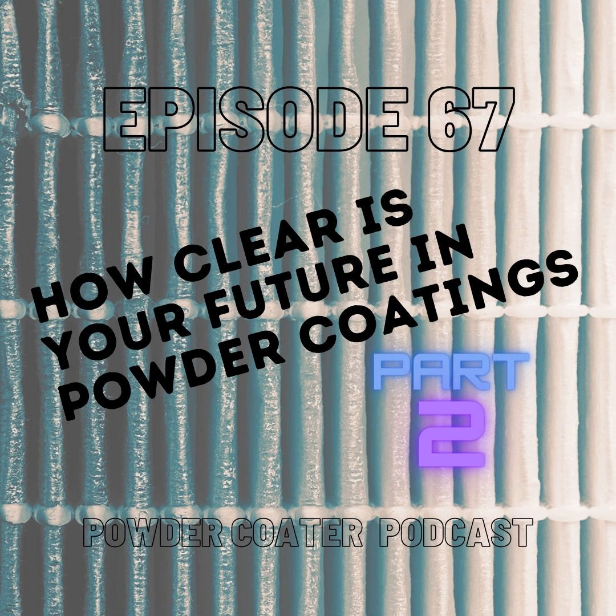Things like your oven walls. People have hit them with their forklift and they're all dented in. If you ever do an infrared camera on it, you're going to see how much heat you're losing. Just feel it, and you'll feel how much heat you're losing. And the entrances and exits, and so many different ways we can look at heat recovery or heat containment so that we can be more efficient. Because the more efficient you are, the less gas you're going to use. Right, that's what this is all about, at least on the curing side.